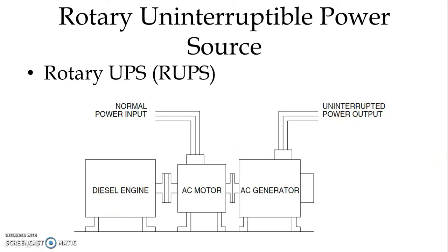In case of loss of normal power, we use the diesel engine as a prime mover. It is connected to the same shaft, and it will start rotating and work as a prime mover to the AC generator, and we will have an uninterrupted power output through the AC generator. Now the shaft is connected to the flywheel, and because of inertia, it has sufficient energy stored until the diesel engine reaches its maximum speed. We have sufficient energy stored in the flywheel to keep it as a prime mover for the AC generator, and we have an uninterrupted power system.